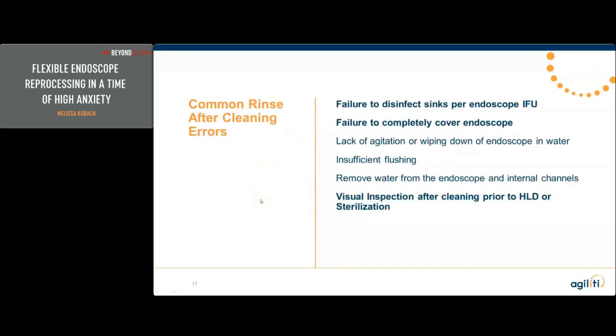Common mistakes for rinse after cleaning: failure to disinfect the sinks per the endoscope's IFU. This is mostly related to one manufacturer. I know that we need to disinfect our sinks after we go through a whole run, but one of the manufacturers has it happening multiple times within the same cleaning event, and it is very difficult, especially if you have a slow sink fill, to do that. So I find people skipping that often.